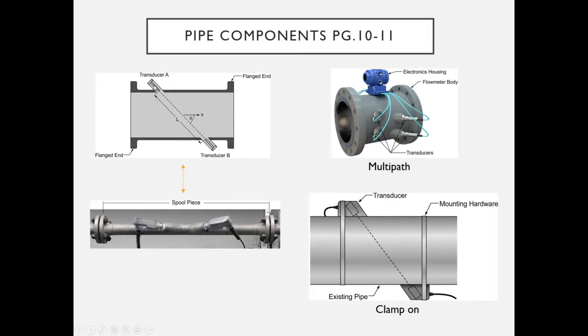If the pipe spool is large enough, transducers on opposite sides work fine. For small pipes, a second solution is a fast-loop bypass arrangement where transducers are on opposite sides of a bypass loop that can be made wide enough to provide the electronics the travel time they need. Both approaches allow ultrasonic measurement on pipes that would normally be too small.